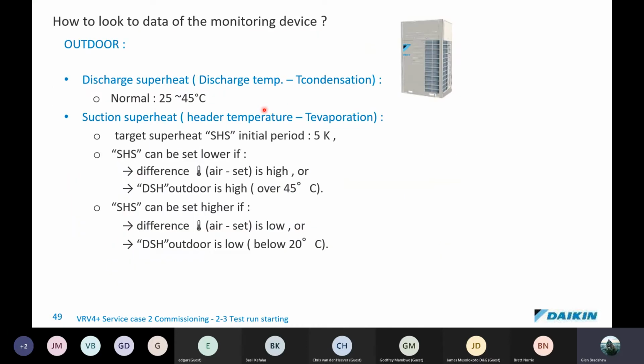All right, so what are we looking at when we have these tools connected? A couple of things need to be monitored. Discharge superheat needs to be between 25 and 45 degrees Celsius. So what is that? Discharge temperature minus the saturated condensation temperature. That's the temperature read from the pressure that you would get off, say, a gauge manifold, and you subtract that from the actual discharge pipe temperature on the discharge side of the compressor. We're looking for a 25 to 45 degree difference in there.